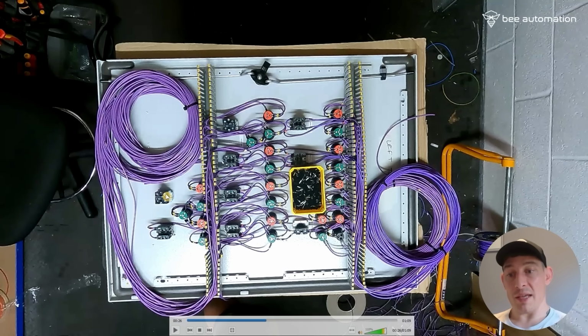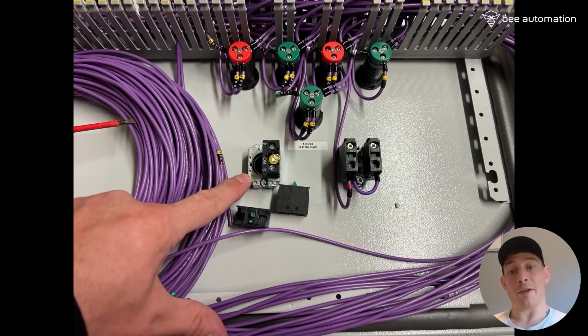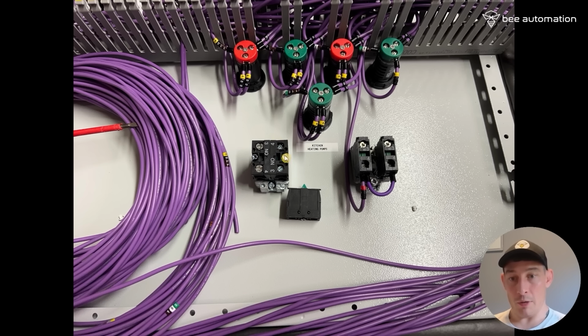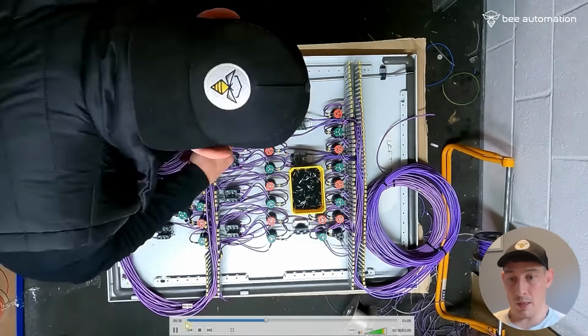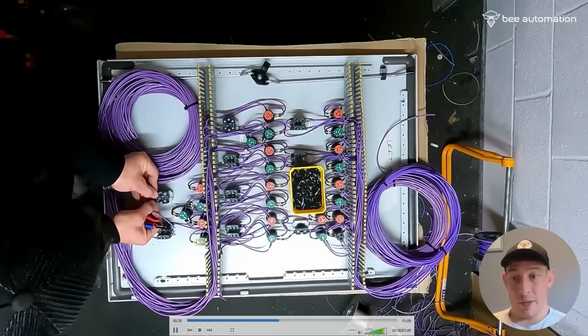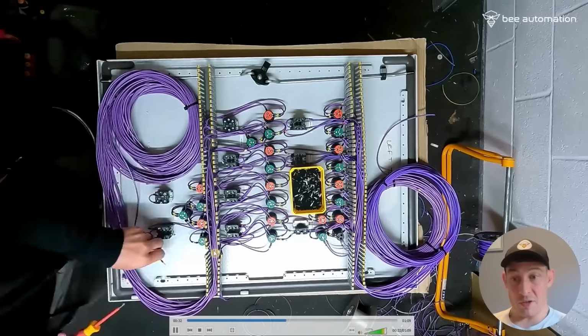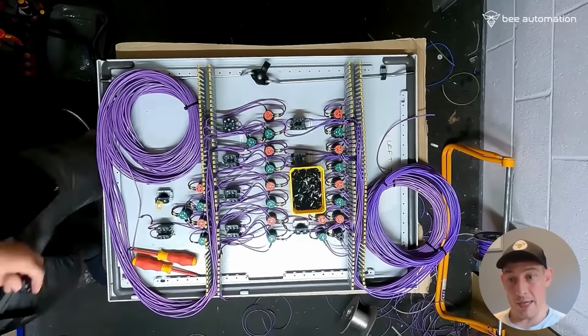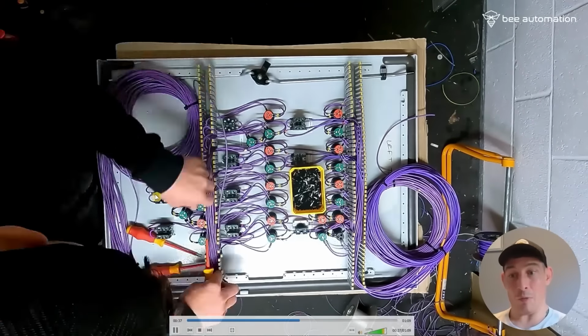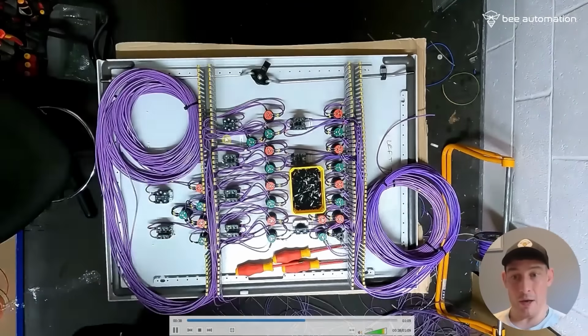Also, you'll notice these 2-position contacts or switches or cam switches, 1, 2, they originally only had one contact on them. So because it's for pump 1 or pump 2, we need to have a second contact on there. So I'm just adding those on here in the video, or have done. And then it's a similar thing with these contacts. You're just bringing a feed in, looping out into the next one, and then over here.